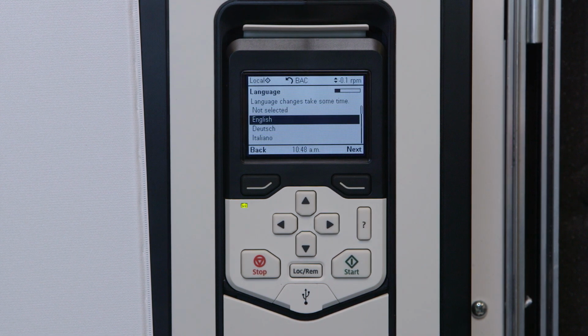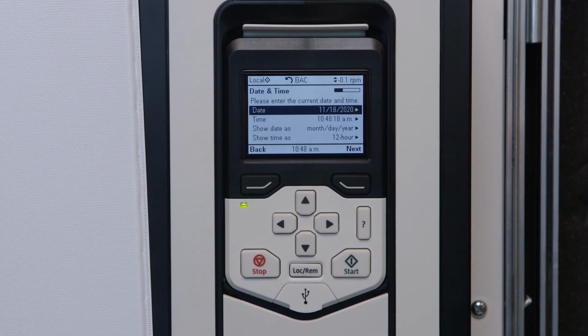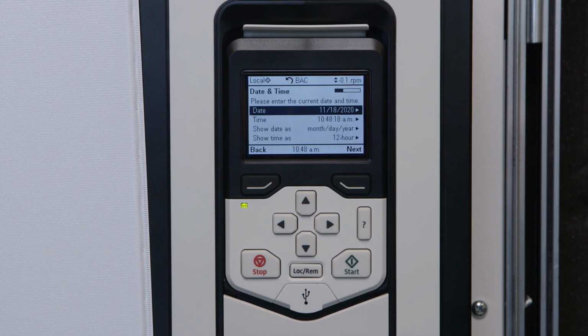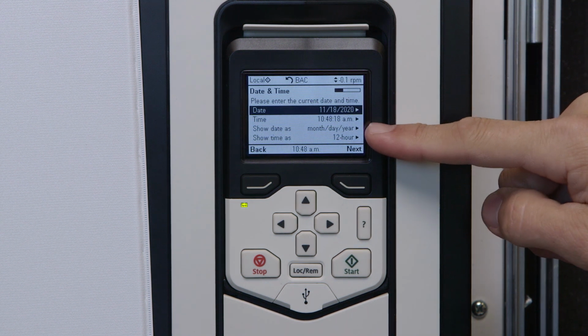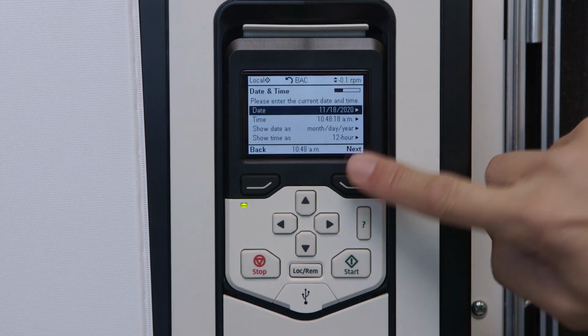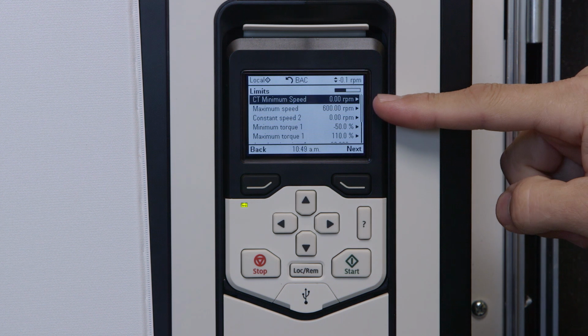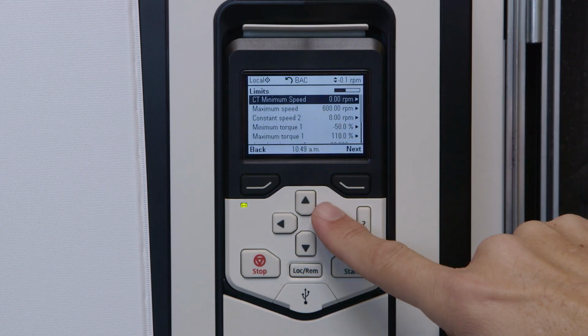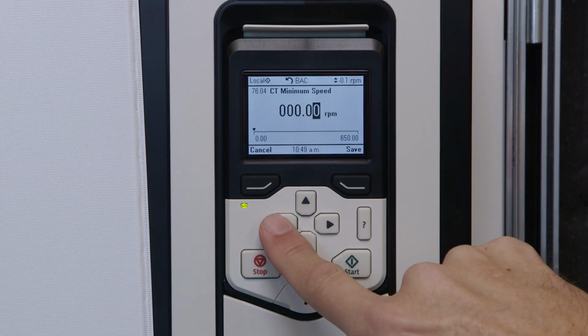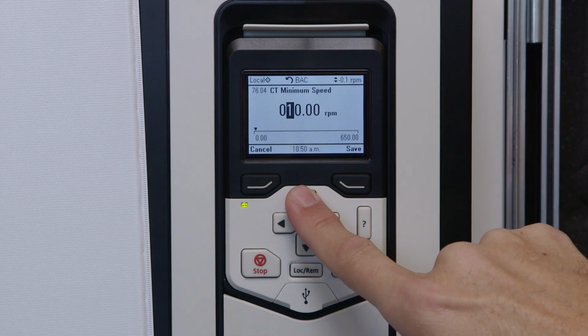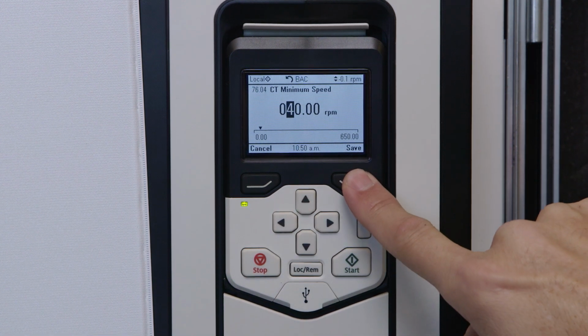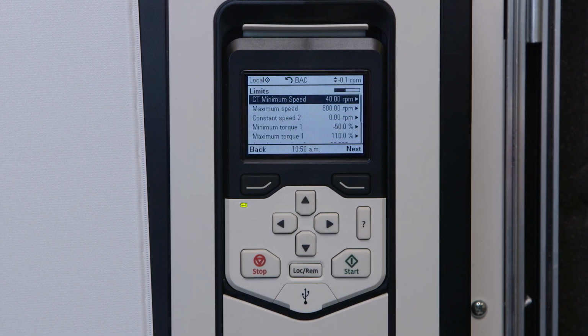Use the right arrow, select the language you prefer to use, and then press Next. Confirm the date and time are correct. Press Next. Now let's set up the motor speed and torque limits. You should now see the limits display. Use the right arrow to change the minimum motor speed. Set the value to 0 for no minimum speed or enter the value desired.